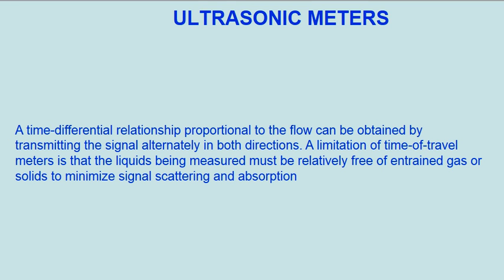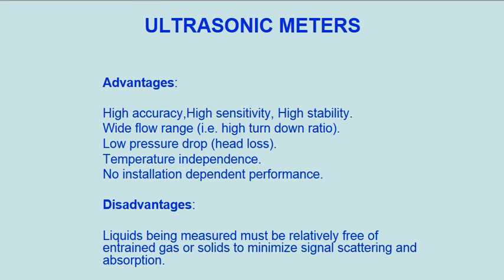A time differential relationship proportional to the flow can be obtained by transmitting the signal alternately in both directions. A limitation of time of travel meters is that the liquids being measured must be relatively free of entrained gas or solids to minimize signal scattering and absorption.